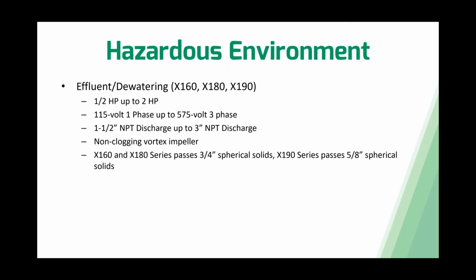So within the effluent and dewatering, we have pumps that go from the X160s up to the X190s, which is a 0.5 horsepower up to 2 horsepower options. When it comes to the voltage and phase, we go from 115 volt up to the 575 volt 3-phase. Now, talking about the discharge, within this effluent series of pumps, we offer standard 1.5 inch NPT discharge, but also you can get these up to 3-inch NPT discharge. All the pumps within this series come with a non-clogging vortex impeller. If solids passing is critical when it comes to these specifications that you're reviewing, just know the X160 and X180 series passes 3/4 inch spherical solids, whereas the X190 series passes 5/8 spherical solids.